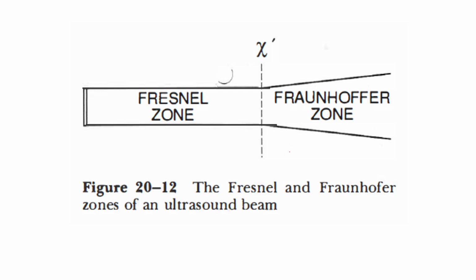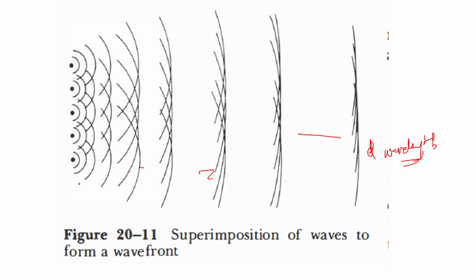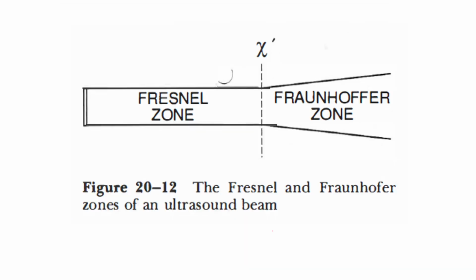One more important thing in ultrasonic waves is that here, if you see, till this part, the waves are parallel to each other. These waves which are produced from five points are seen parallel to each other. From here, the parallel is almost lost. Okay, that is, at least for some distance, the waves will be parallel to each other. This parallel zone is called the zone of Fresnel, and here they are becoming diverging to each other, and this diverging zone is called the zone of Fraunhofer. Okay, so an ultrasound beam will consist of two zones, the zone of Fresnel and the zone of Fraunhofer. The zone of Fresnel is the parallel component, which is called the near or Fresnel zone, whereas the diverging component of the beam is called the Fraunhofer beam.